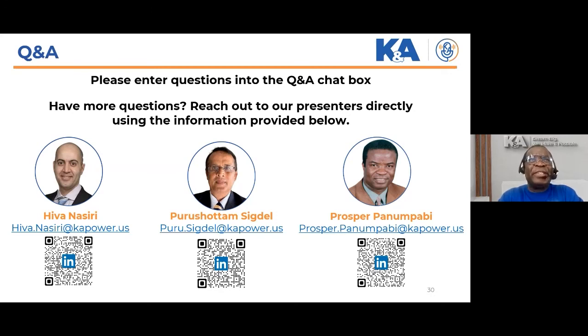In the video we saw, if you go back to this, we have a transmission line interacting with two devices, two relays. One distance relay is modeled inside the simulator. This is called the computer modeled relay. At the end of the transmission line, we have a physical relay. In this case, it's a hardware SEL-421. This is called hardware in the loop.